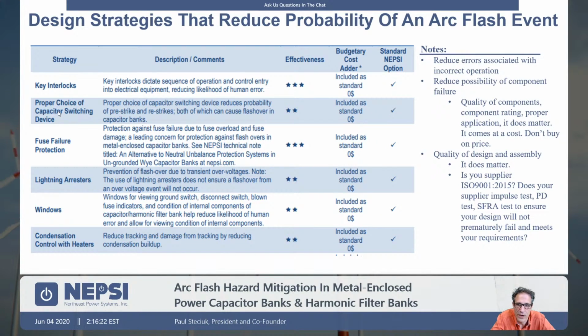We see proper switching, proper choice of switching device, as being very important. As standard, NEPSI will always up the voltage rating of their switching device. If you have a 15 kV system, we no doubt will be using a PS25, a 25 kV rated switch. Why? Because it's less likely to restrike. We have found that restriking of capacitor switches is the number one cause of case rupture within capacitors. So a capacitor restrike leads to case rupture. Case rupture leads to the possibility of an arc flash event.